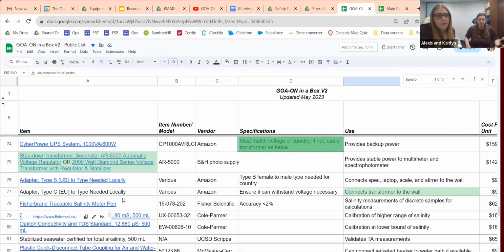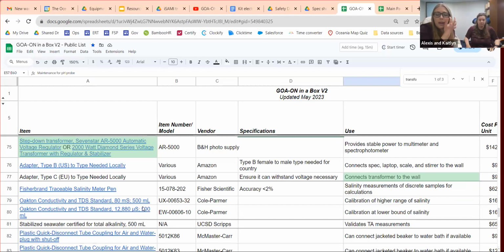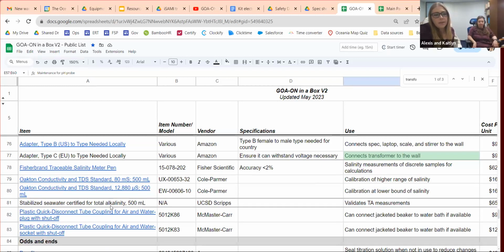To support other measurements that you're going to need to do your CO2SYS calculations, we're including a salinity pen, so you can measure the salinity of your sample, as well as standards to do calibration for that salinity pen too. And then we have reference materials from the Dickson lab for total alkalinity. That comes with a certified value that you can find online. The box may include the website link for that, but we can also point you towards it so you know what the value of your reference material for that particular batch should be, and the value that you should be getting when you're running that reference material in between your own samples, and then can understand how close or far you are.